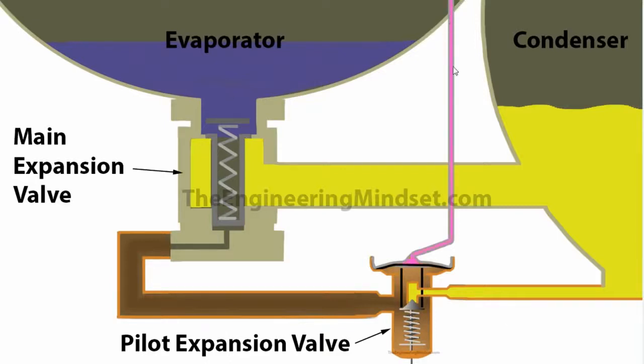So as the pressure increases in the capillary tube and it starts to build up and push down on this valve, you can see inside the valve there is a diaphragm which is connected to some push rods and then onto this valve head, which is also spring loaded. There are a few variants of this design, but this is probably the simplest and one of the most commonly used. So as that pressure increases and starts to push down on that diaphragm, it pushes against the piston rods, and these rods push the valve head down, and that causes a slight gap to form there, and this allows refrigerant to start flowing out.